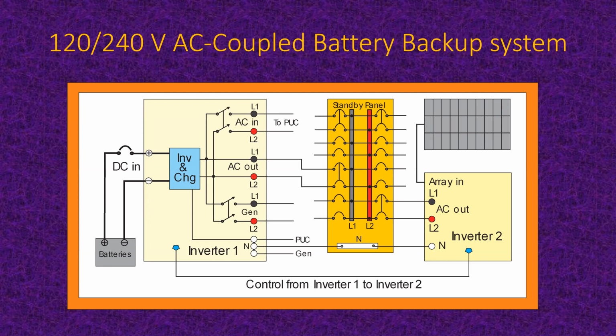So now the next thing is utility is down and it's nighttime. The only possible place we can get any electricity for those poor loads in the standby panel now is from the batteries. So that's when the inverter and the batteries get together and say, okay, let's go guys, it's time to make some electricity. And they make that AC and they power up those standby loads. And at 3 o'clock in the morning, the battery voltage has dropped to 48 volts, and the inverter notices that and says, oh boy, these guys are getting tired.